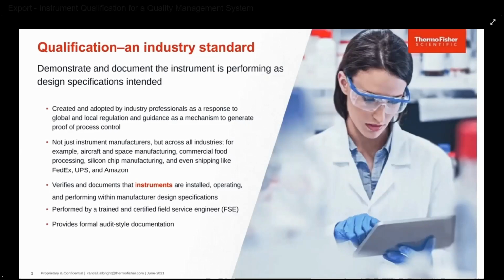An example is Amazon. When they build out a local warehouse, they install what is called a conveyance system to move orders from fulfillment to logistics for delivery. They perform a qualification of the conveyance system and computer system validation of the software and computers that employees use to process your orders. Our Thermo Fisher Scientific qualification documents that the instrument is installed, operating, and performing to the manufacturer's design specifications. It is performed by a trained and certified service engineer, such as myself, and you'll receive a document as well as supporting attachments.